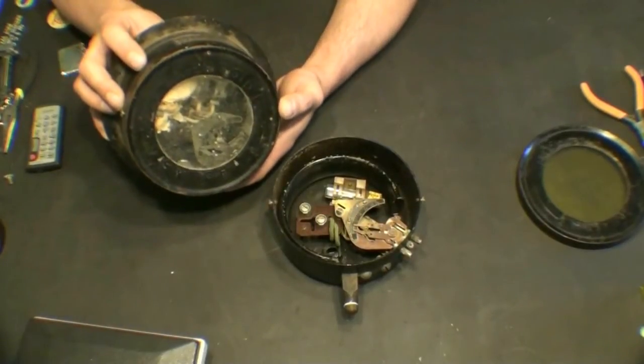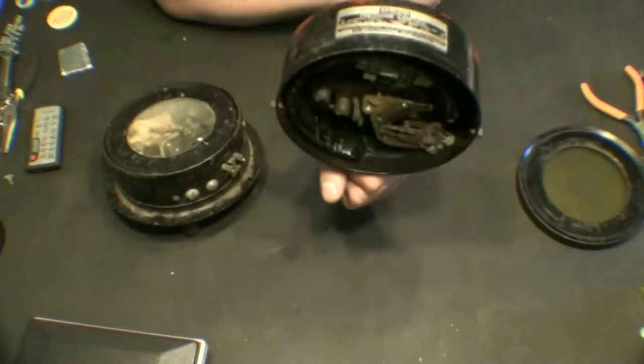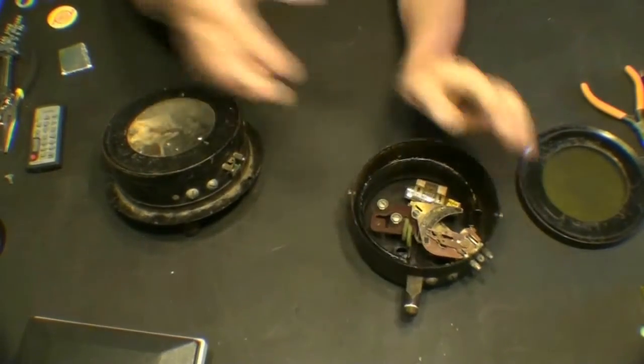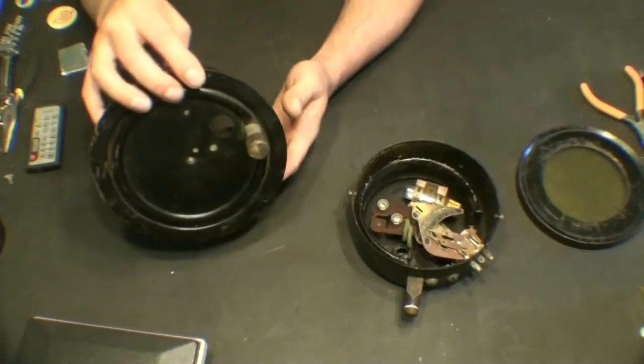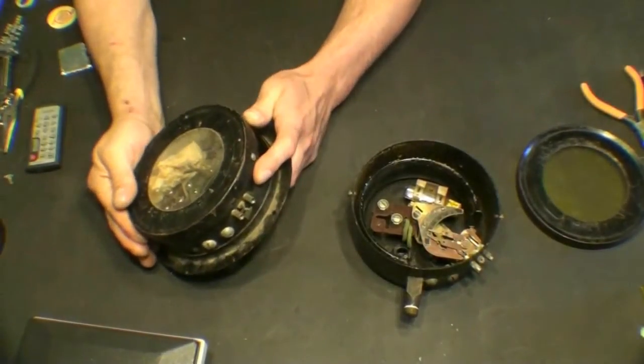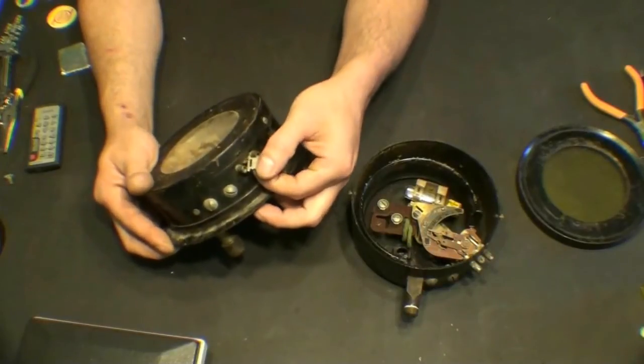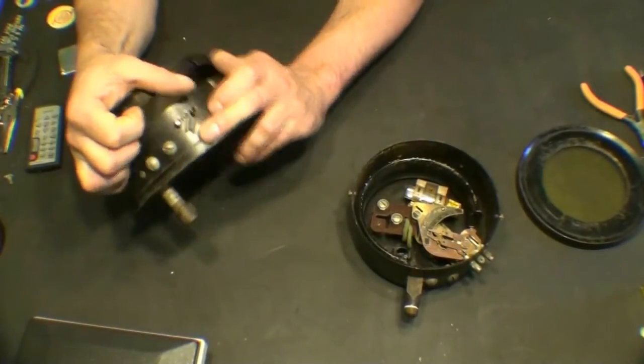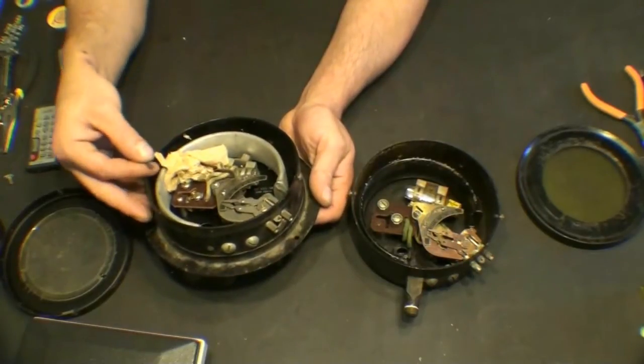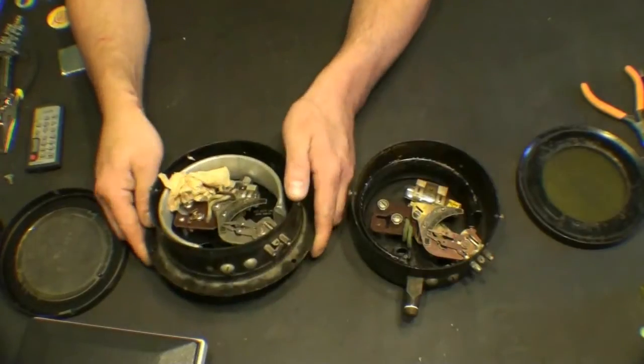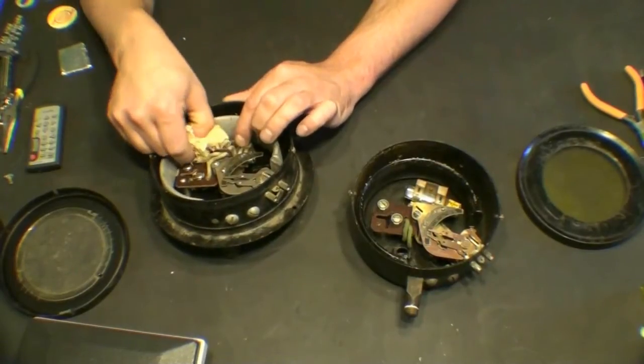This one is a DA21-3 and this one is a DA64-3. This one would just sit on your pipe or whatever, and this one is actually a panel mount switch that has the pressure connection in the back. This one here appears to be new because it still has the little lock tab attached with a wire, and there is still the tissue paper wadding in there to keep the mechanism from moving during transportation. So I'm going to pull this out just so we can get a better view of it.